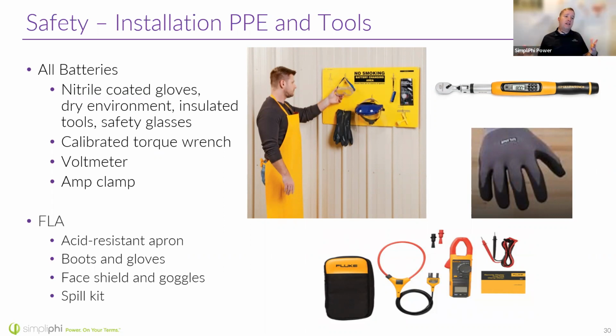And even if you don't have an insulated torque wrench, there are breakers on the batteries, so turn the breaker off on the battery. Even if you happened to short out the negative and positive lugs with a non-insulated torque wrench, you're not going to get a big pop in your face because the battery is dead - the internal breaker is off. I like the internal breaker too, it's an extra level of safety. Also, if you ever have to troubleshoot, you can turn off that breaker and isolate individual batteries in a battery bank, so you can start getting out your fluke meters and metering things here and there. It says calibrated torque wrench, so make sure you take it to the shop to calibrate it - I think a lot of times you have to send that in.